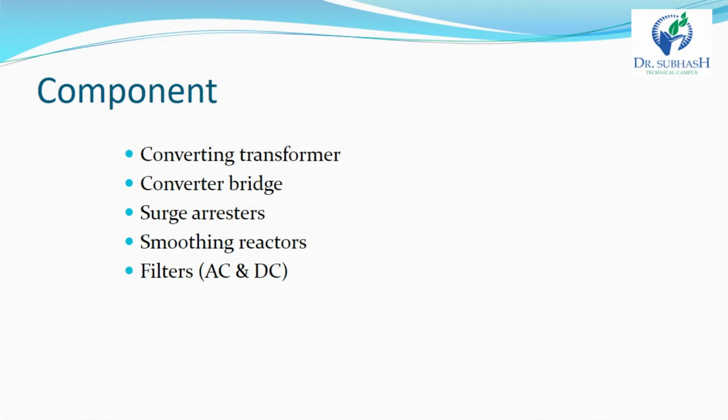In this converter bridge, in the converter valve, the modern HVDC converter has a 12 pulse converter unit and the total number of valves in each unit is 12. The valve is made of series connected thyristor modules. The number of thyristors depends on the required voltage across the valve, and the valves are installed in a valve hall and are cooled by air, oil, water and so on.